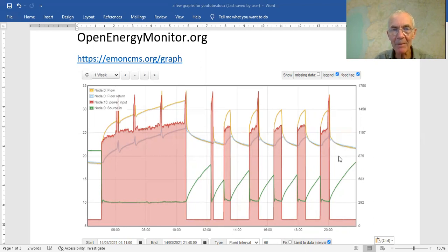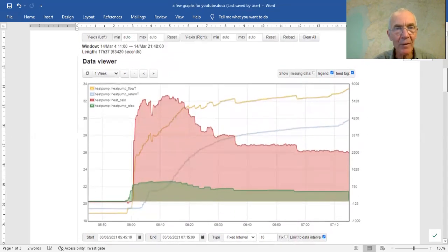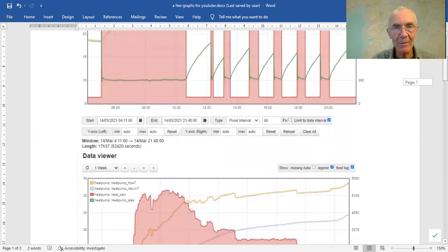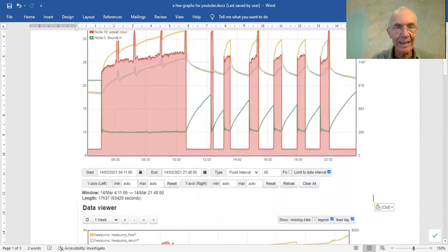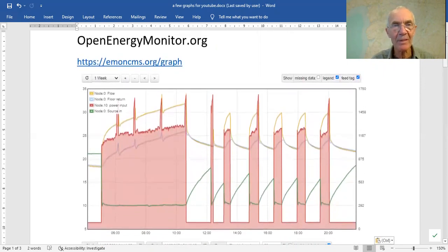That cycling could be an issue we may want to minimize, or not, depending on what we're trying to do. The graph below involves a heat meter, so it's showing the actual heat output and the power input. You can visually see the COP, which is really useful. I was doing some analysis here to look at what happens at startup, and there are various statistics you can extract, which is really useful. You can zoom into certain windows and look at the performance and average over that window. That's the website to look at — there's everything you want to know there.